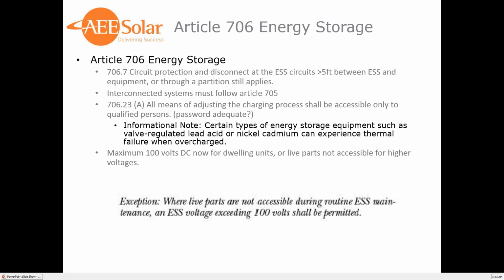Maximum 100 volts DC now for dwelling units, or live parts not accessible for higher voltages. So you can use higher voltages, the LG battery and the storage, for example. The LG battery is a 400 volt nominal battery, but all the live parts are not accessible and protected, so it's allowed. So essentially it just bumped up the normal 48 volt to 100 volt DC.